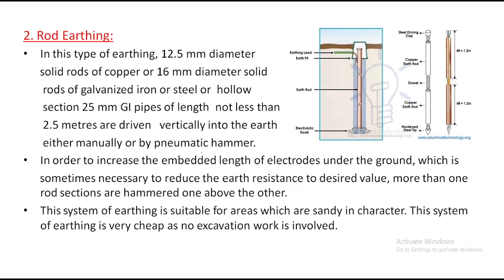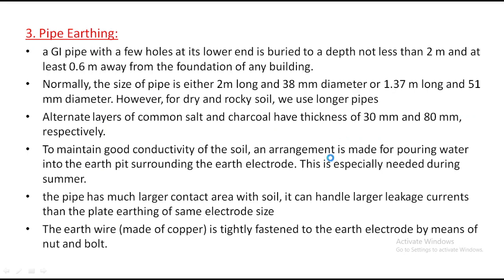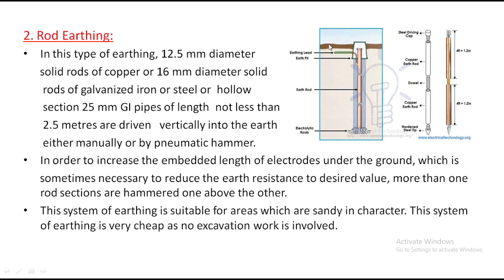Next, rod earthing. As the name itself says, in place of this we will use rod earthing. Look at here, we are using a rod as our earth material. This is the rod and this is the ground. The earthing lead, meaning the earthing wire, is connected to this point and this will be grounded, and this is the earth rod. Electrolytes will be used here. The top point is called the steel driving cap, and this is the copper earth rod. Inside there is a dowel and the copper earth rod. The last point is called the hardened steel tip.